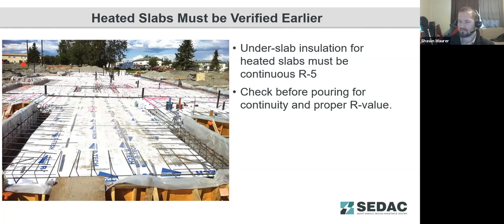If you're pouring a heated slab, it's very important that the insulation and vapor barriers underneath that slab are properly installed and that you don't have errors with that installation. Check for continuity of the insulation underneath the heated section of the slab, making sure it's R5 at a minimum. Again, we like to stress that R5 minimum is the energy code requirement. The energy codes are a grade of D for your building. It's just passing. Ideally, you're going to design for a little more efficiency and reduce the energy consumption of the building more than the energy codes would prescribe.